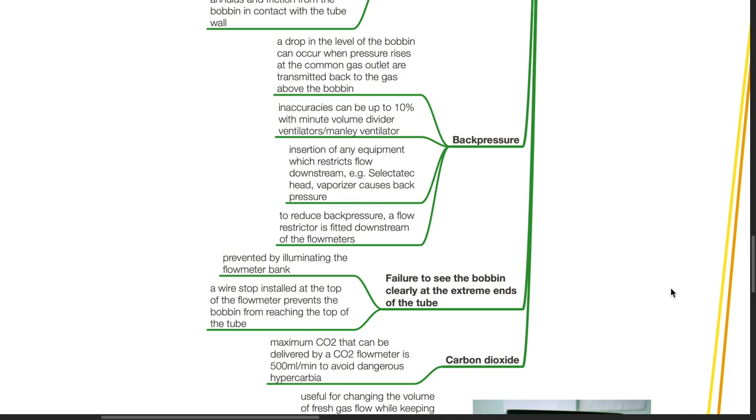Insertion of any equipment which restricts flow downstream such as the Selectatec head or vaporizer causing back pressure. To reduce back pressure, a flow restrictor is fitted downstream of the flow meters.